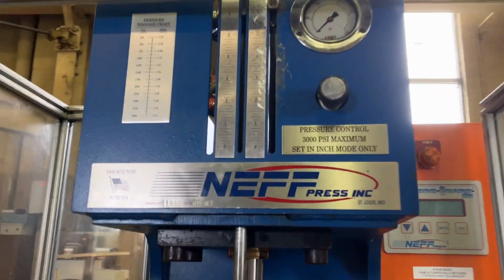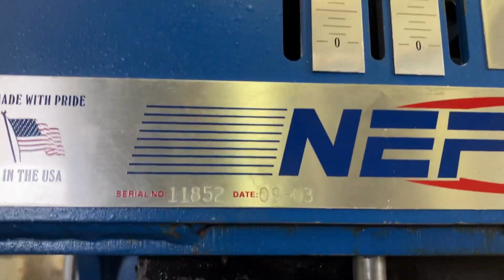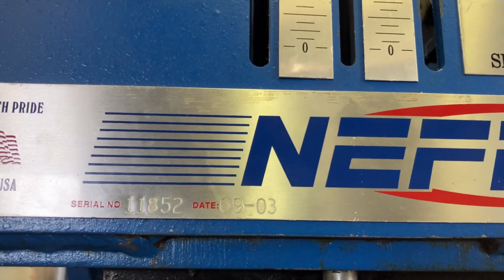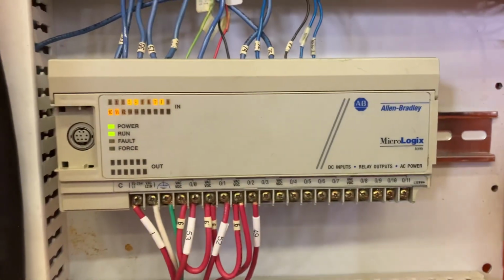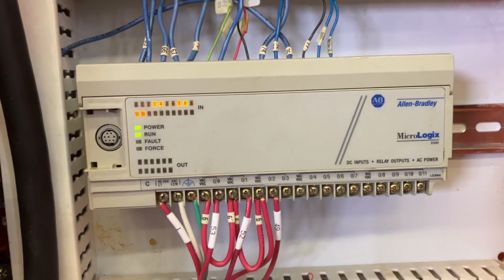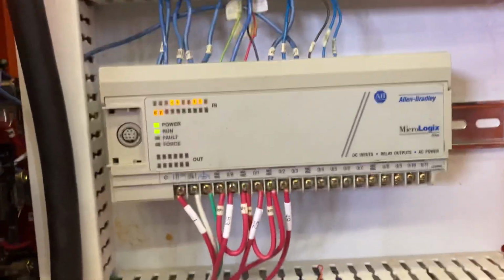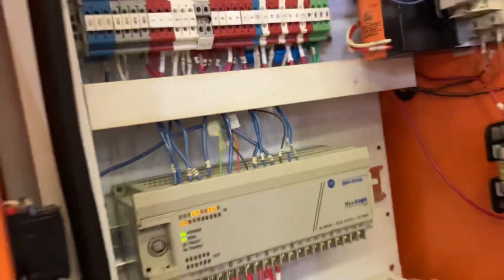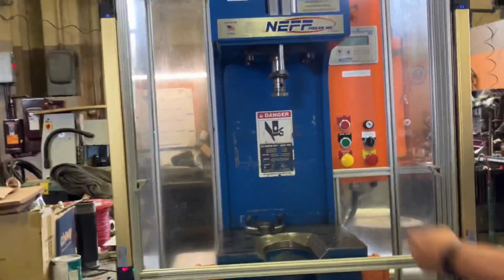Real quick video to show a Neff 3.5 ton machine. The hydraulic PLC was giving us error messages, so we replaced it with the good old Allen Bradley. Everybody loves them, Micrologix PLC. Simpler, easier, solved the problem. Let's run it through the paces, please, sir.